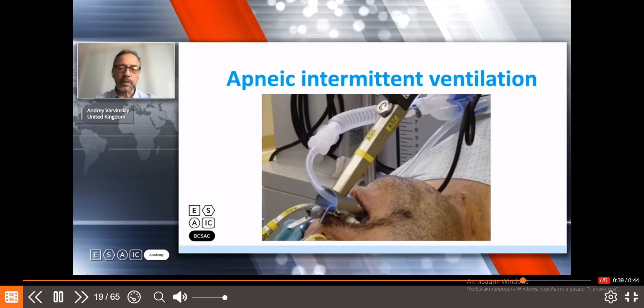There is a Sanders injector or VBM Manujet. Both of them are very similar. The Sanders injector has been around for ages and ages. They both have a source of high pressure oxygen, up to 4 atmospheres, 4 bar, that the standard oxygen supply provides. They have a regulator that can regulate the pressure. They have a lever that we press on to initiate the breath in.